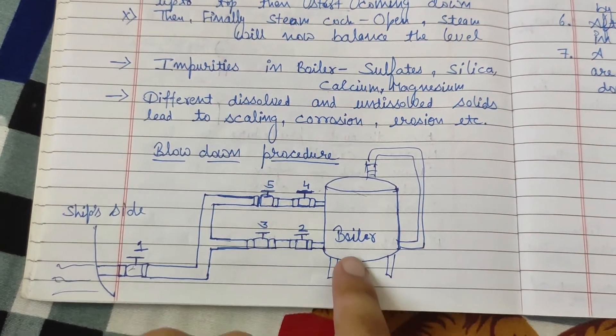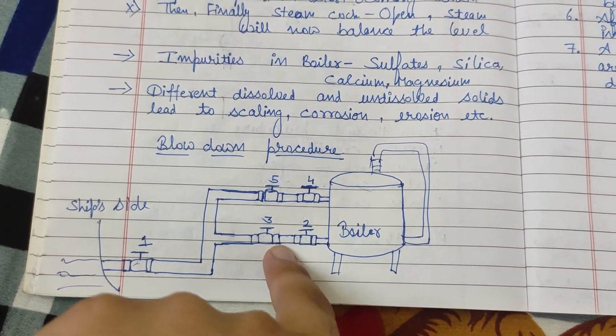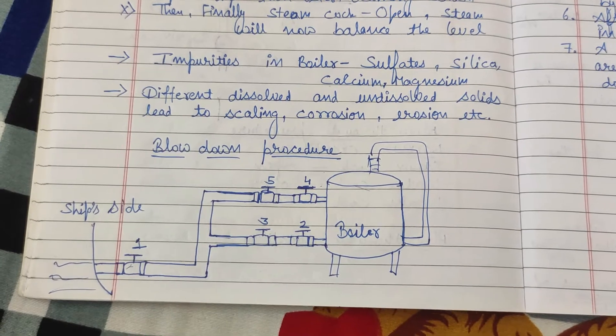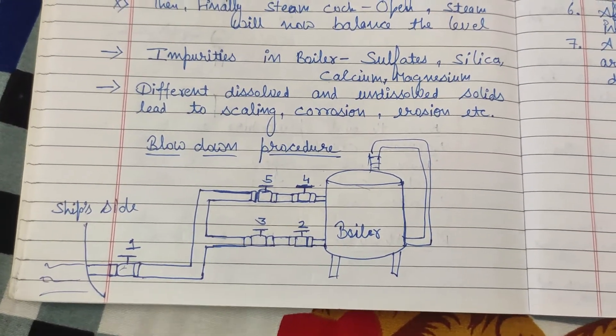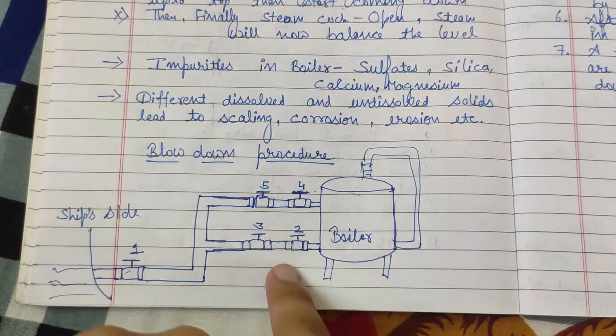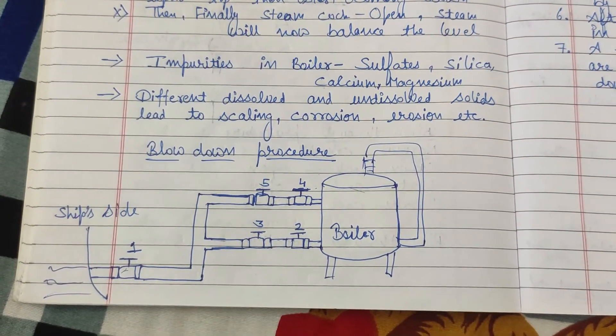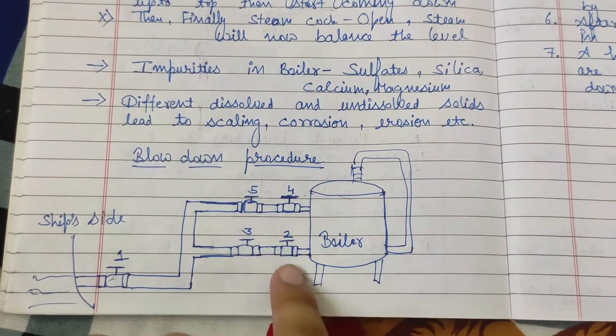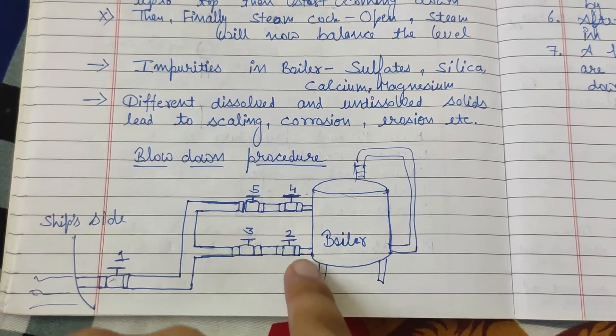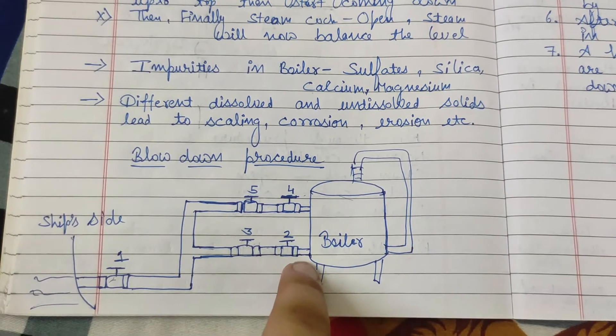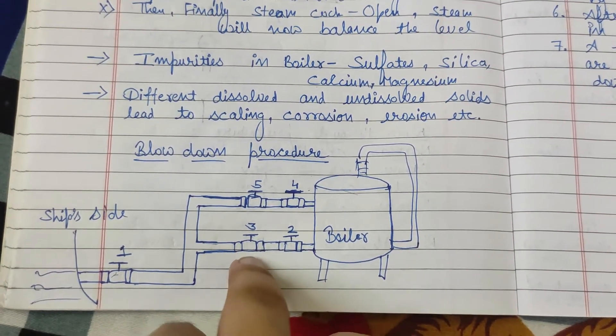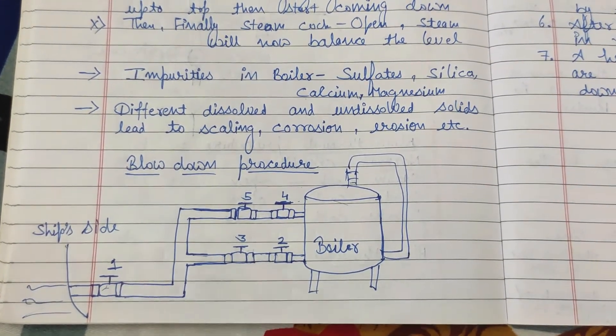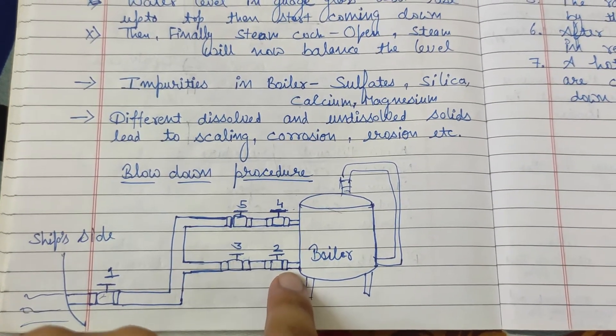With high-pressure, high-temperature water coming through, we open the third valve only by a crack opening to control the amount of water going overboard. We use crack opening on this valve because the pressurized water damages the valve seat. This is our primary valve and we don't want it damaged, so we open the second valve fully and only crack-open the third valve to control the flow.